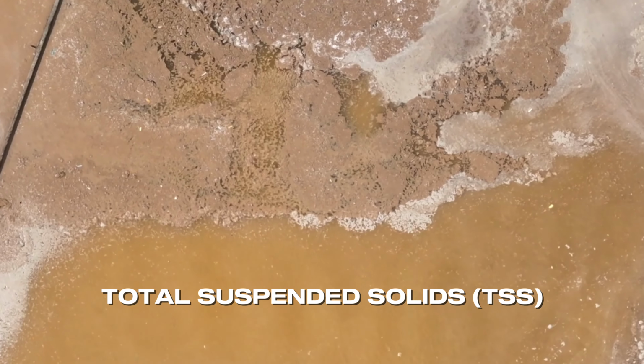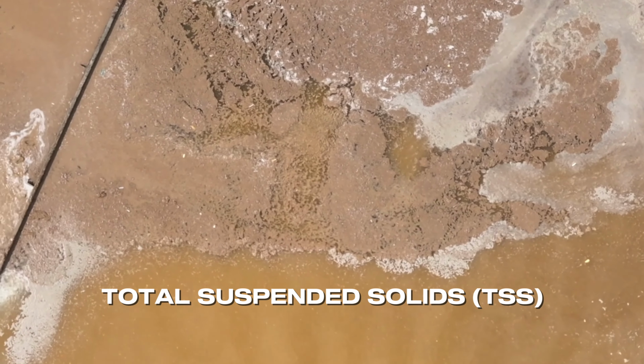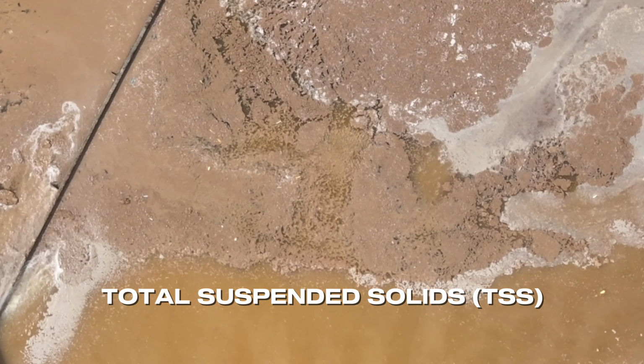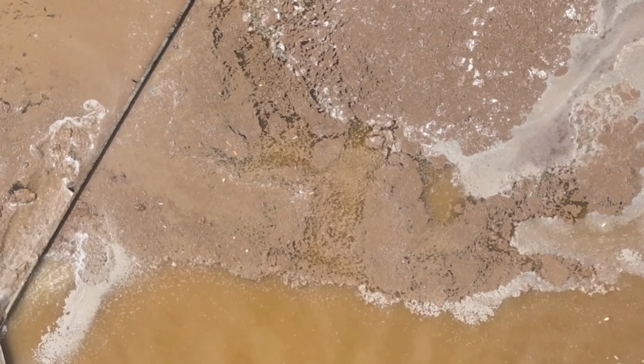Additionally, if the volume of incoming wastewater exceeds the plant's design capacity, it can overwhelm downstream filters, causing blockages. Total suspended solids particles can physically clog screens, pumps, and pipes, leading to increased maintenance and potential equipment failure. Furthermore, a high load of organic TSS directly increases the volume of sludge that the plant must handle, process, and dispose of, thus driving up operational costs.